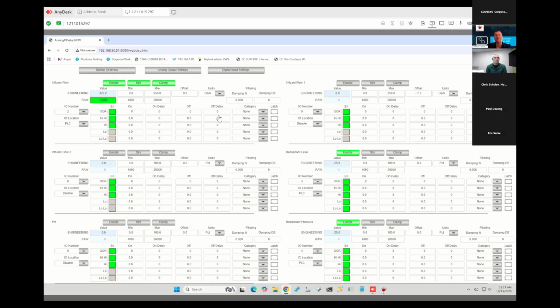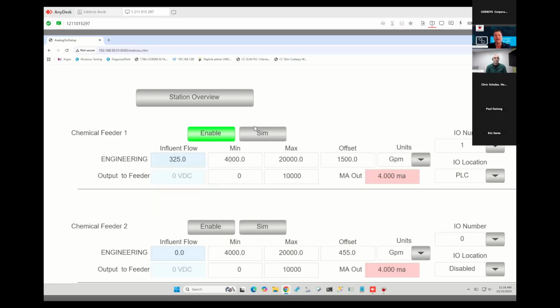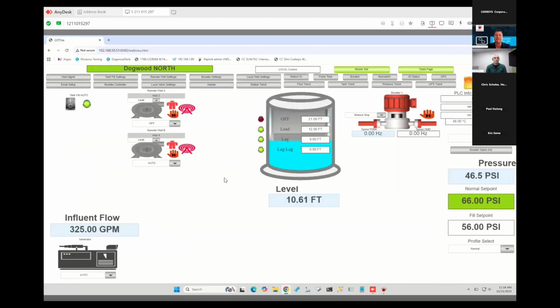Can also come in and change all of my set points, all of my alarming, and simulate. So we've got the simulation mode built into the product directly so that we can simulate and see what might be happening before putting this out in a real world environment. Same on our analog outputs. These are mostly used for chemical feeders. So we're mapping to the chemical feeders here, still scaling, and then showing the customer the actual milliamp output that they're getting from that PLC, that controller.